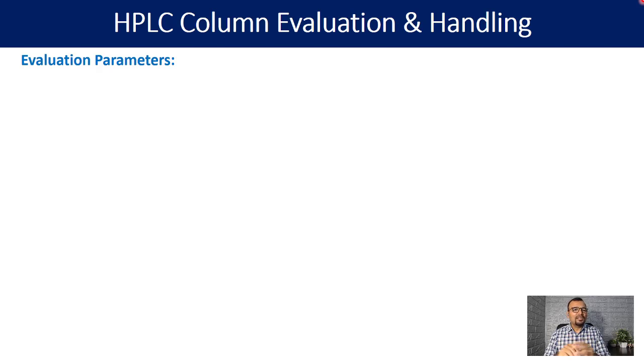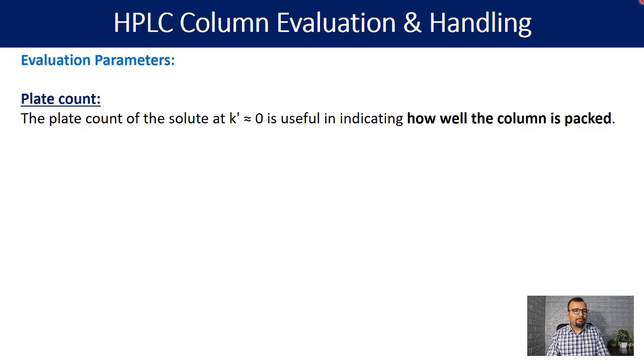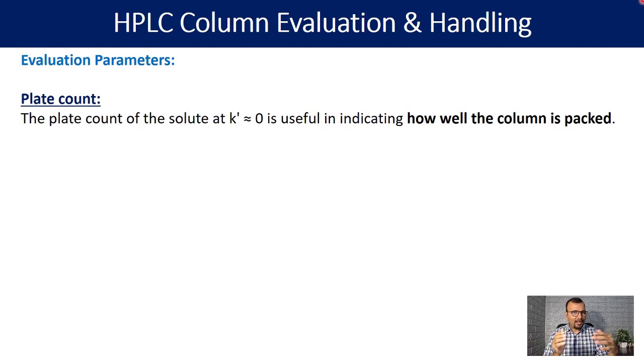Let us now discuss some of the evaluation parameters. The first one is plate count or efficiency. The plate count of the solute eluting at k' equal to 0 — meaning the compound eluting at void volume or early eluting compound — is generally useful in indicating how well the column is packed.